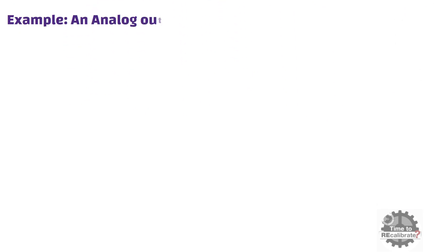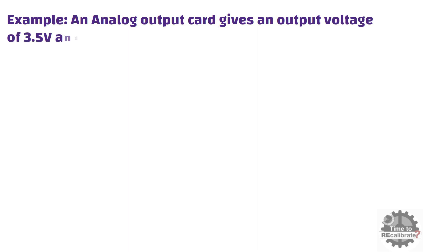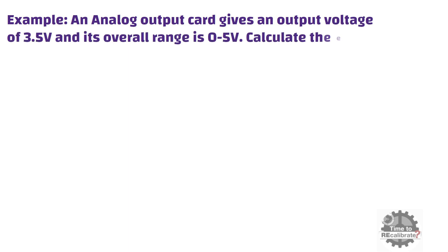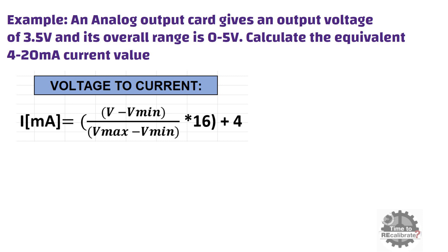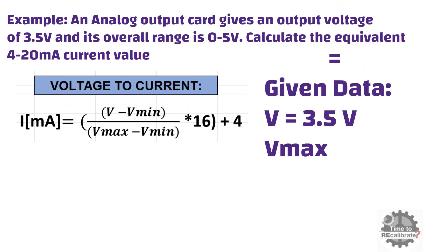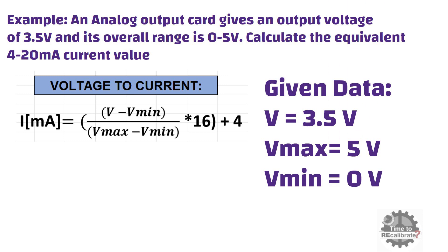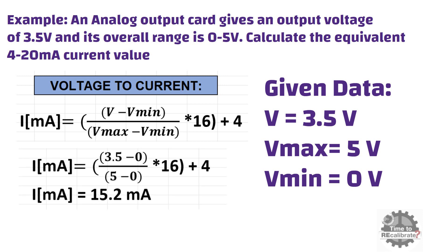For example, an analog output card gives an output voltage of 3.5 volts, and its overall range is 0 to 5 volts. Calculate the equivalent 4 to 20 milliampere current value. The given data is: V = 3.5 volts, Vmax = 5 volts, and Vmin = 0 volts. Putting all these values into the equation and doing the math, you will get 15.2 milliamperes. In other words, when voltage is 3.5 volts, the current value is 15.2 milliamperes.